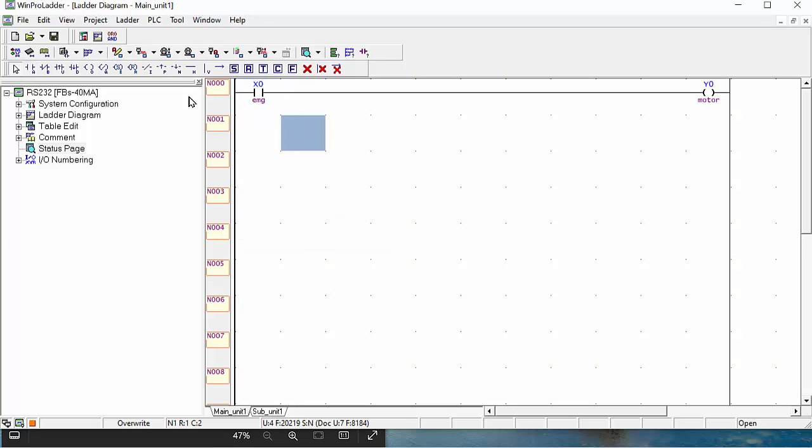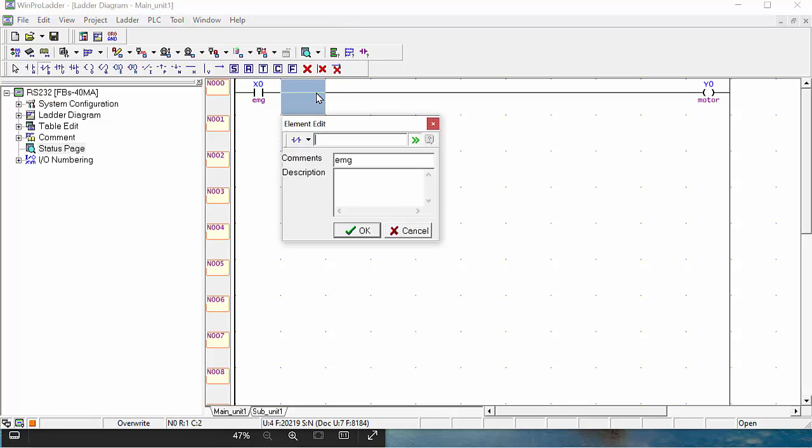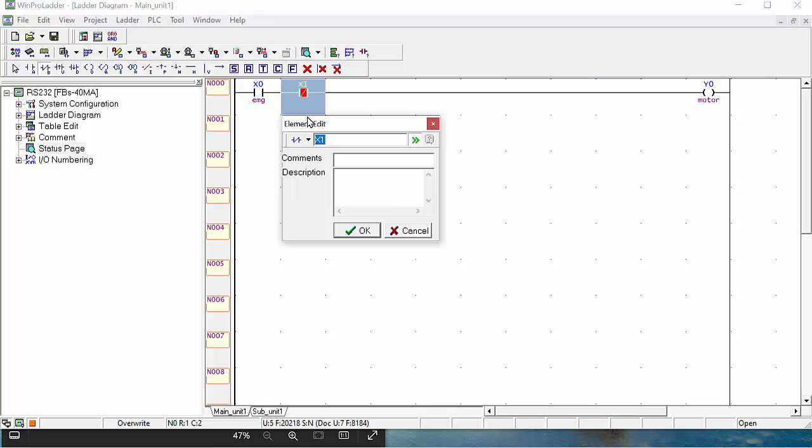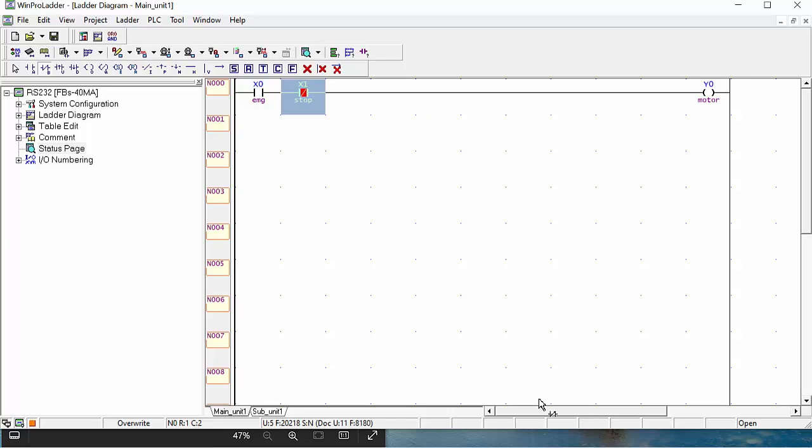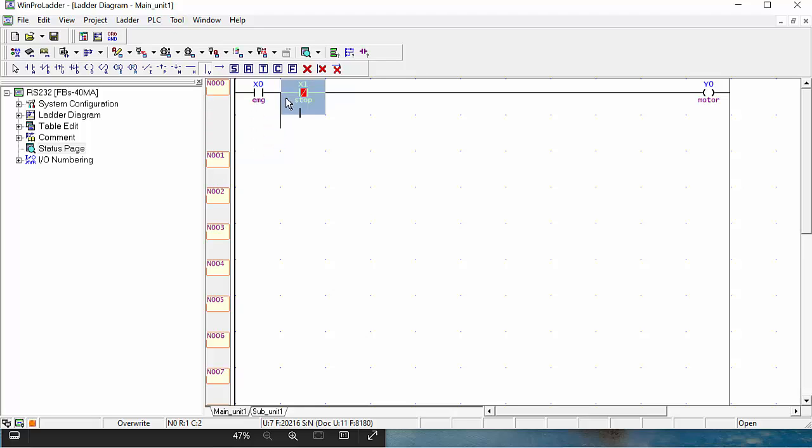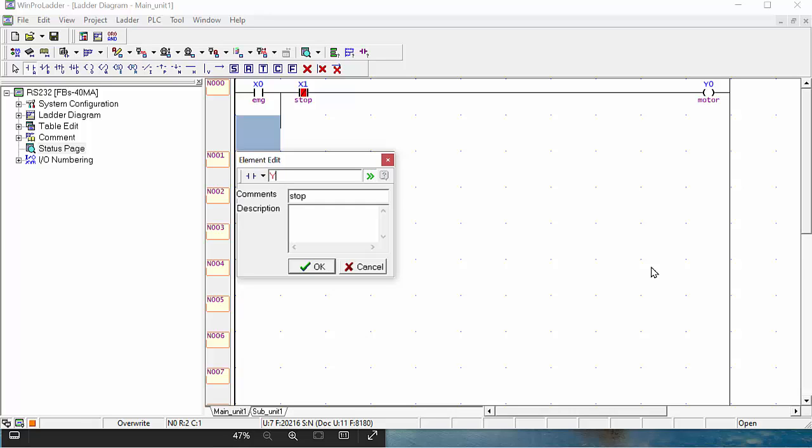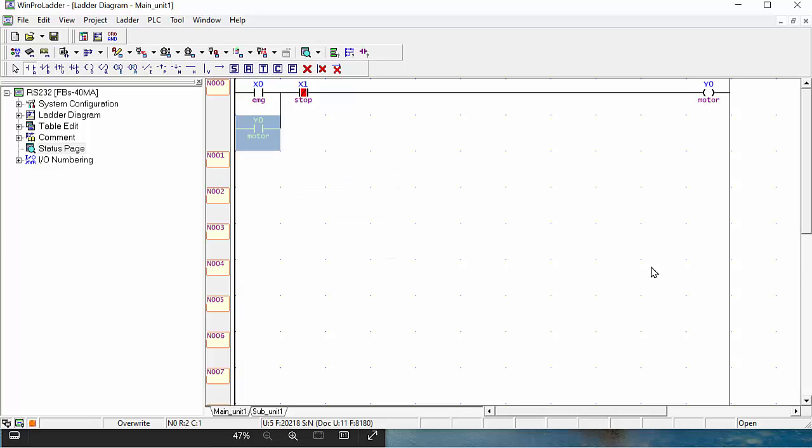We will make a small program for on and off button. Next, you have to take one close button here. This is also asking for address; I will give X1 for my close button, and you can give the comment. You can give stop button, stop comment. Now your two bits and one coil are ready. For holding, if you like to make this program, simply make one row here and take one more contact for your program. Here you can take the address Y0 for holding address.